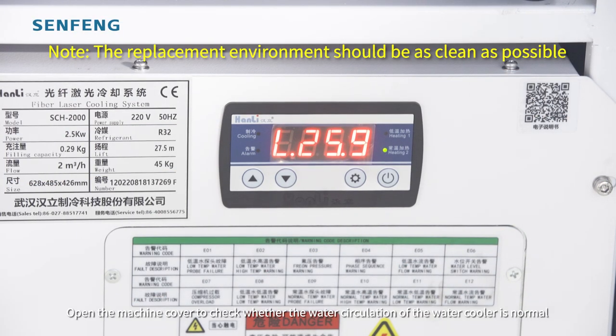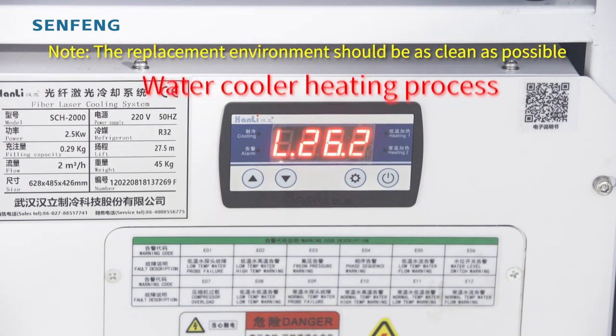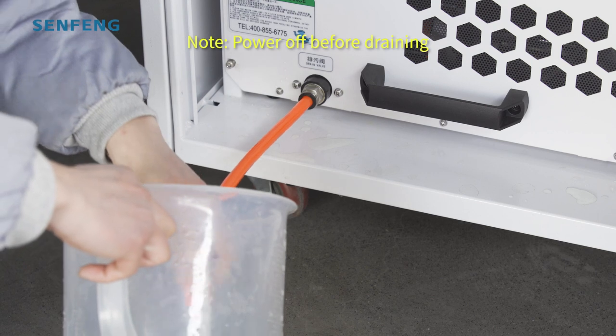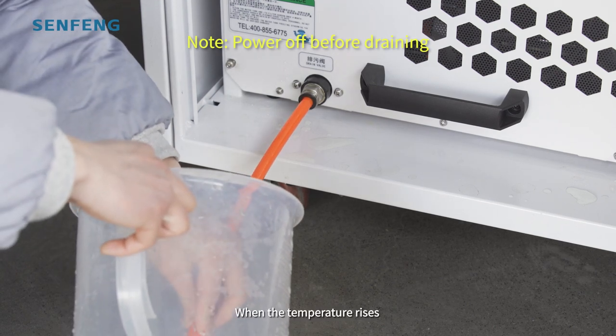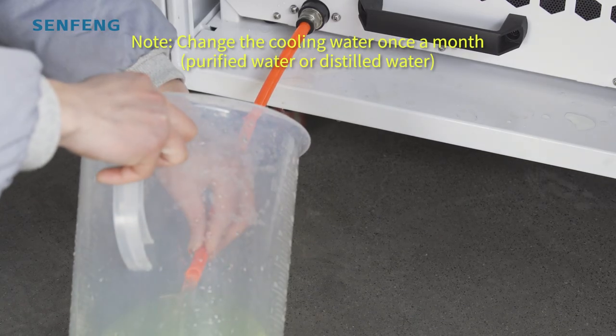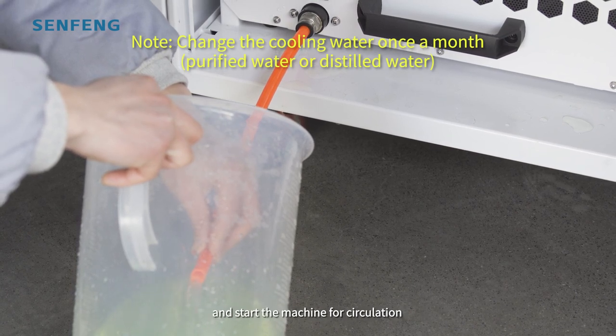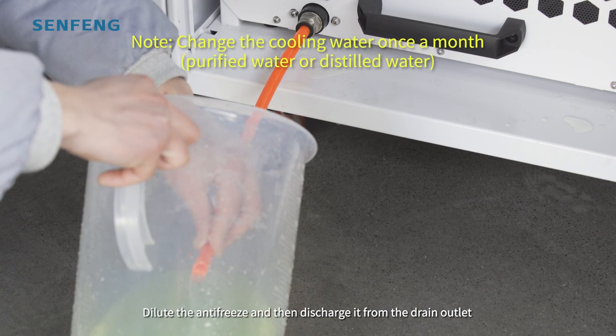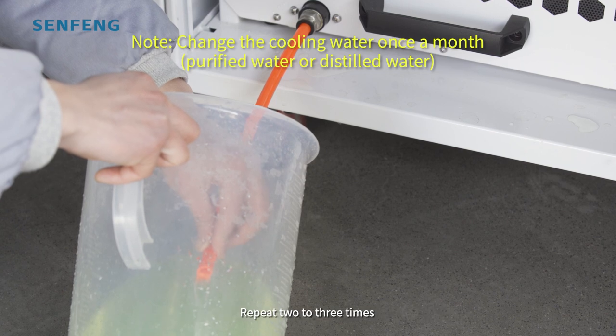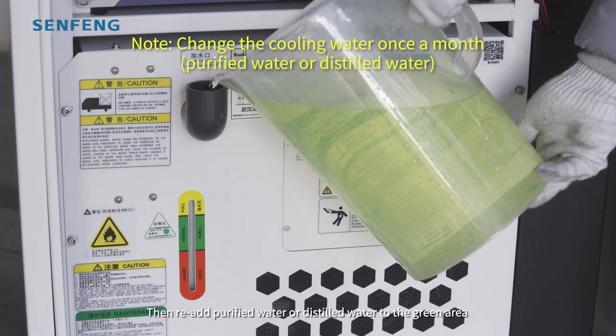Open the machine cover to check whether the water circulation in the water cooler is normal. When the temperature rises, the drain valve should be opened first to drain the antifreeze in the chiller. Add purified water or distilled water from the water inlet and start the machine for circulation. Dilute the antifreeze and then discharge it from the drain outlet — repeat 2 or 3 times. Then re-add purified water or distilled water to the green area.